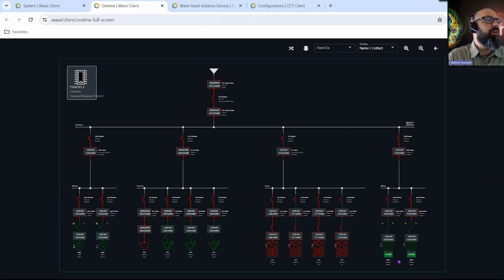Great. Okay. So in this situation, we've got the primary load for our facility online being fed from the grid. We haven't added any PV generation yet with the emulator, but as that becomes available, we'll start ramping that up. And we'll see that as more and more renewable energy becomes available, we'll start closing the breakers to those controllable loads there, kind of just in the middle left of our one line. And we'll be either charging those electric vehicles or creating some hot water or whatever the case may be, where we're able to take advantage of that instead of curtailing our production.